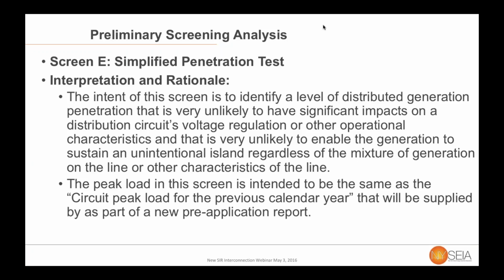The origin of the 15% number comes from the fact that when they were developing screening methodologies, they looked at a variety of different feeder types, and what they saw was sort of as a rule of thumb, the minimum load on these circuits was on the order of about 30% of the peak load.